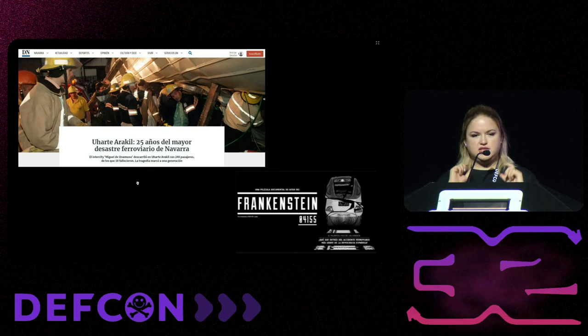But when the train passes through the beacon, an inductive coupling is produced between the first coil that transmits 111 kilohertz, the second coil that receives that signal, and the third coil that is on the tracks, which modifies the inductive coupling to another frequency, the frequency that this beacon is configured with. It's easy to understand. Yes? Of course. Okay? Yeah. It's okay. Easy.